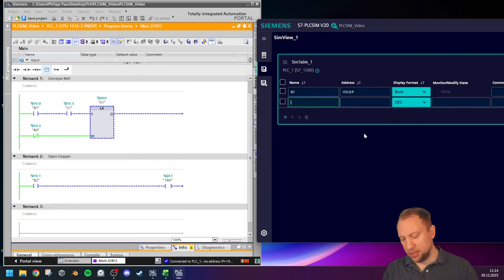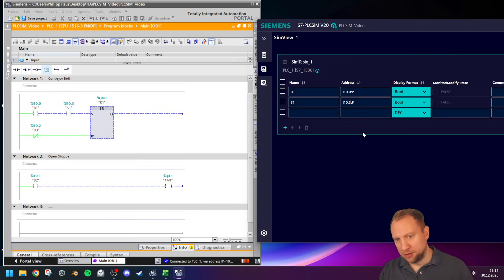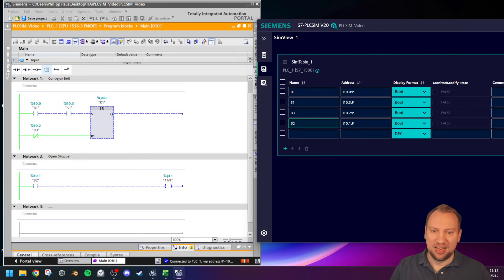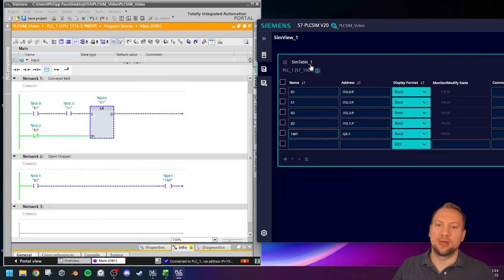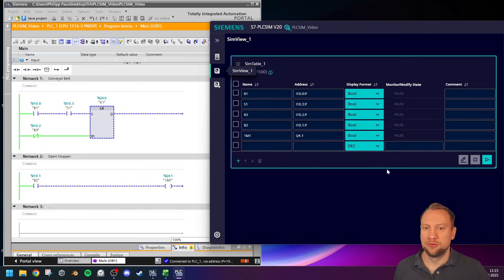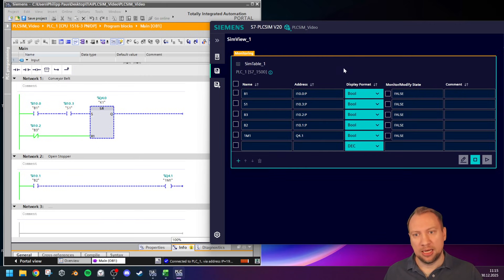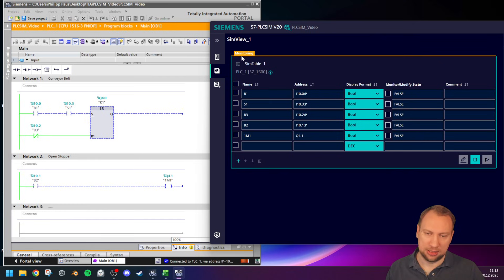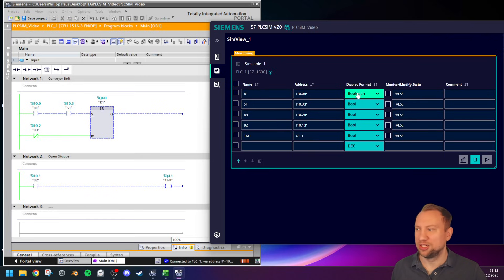I will add a new Simulation Table. In the simulation table, I can enter my tag names — for example, B1 with auto-complete — which is the first sensor. Then I have S1 (the push button), B3 (another sensor), B2, and so on. I can load all my tags, and I will show a more convenient way to do that shortly. Now I press the play button, which will bring the simulation table online so I can monitor it.